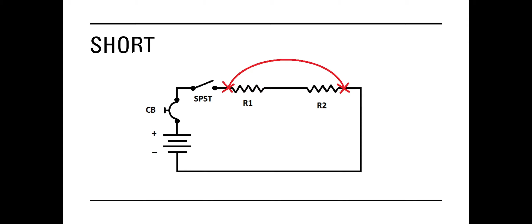If a short occurs in the resistance or load, it may cause an increase in current, and the fuse will melt, or the circuit breaker will pop open. This is the purpose of the protection device: it changes a short to an open to prevent the circuit from catching fire or melting from too much current. When this happens, it is referred to as a short to ground. In most cases, a short can be identified without using a meter, just by observing the symptoms.